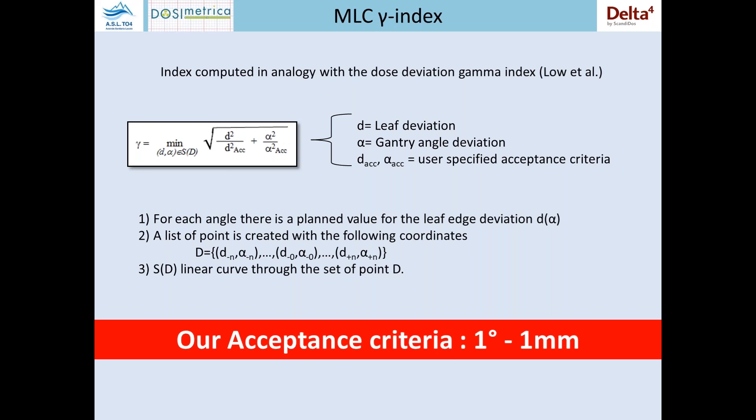We talked about the MLC gamma index — but what is the MLC gamma index? It is an index computed in analogy with the dose deviation gamma index, as presented by Low et al. It evaluates the leaf deviation with respect to the gantry angle. For each gantry angle, there is a planned value for the leaf edge deviation. The user can set acceptance criteria for this parameter. In our institution, we chose an acceptance criteria of one degree per one millimeter of distance.